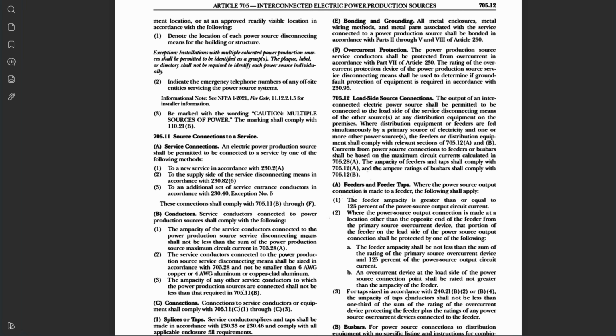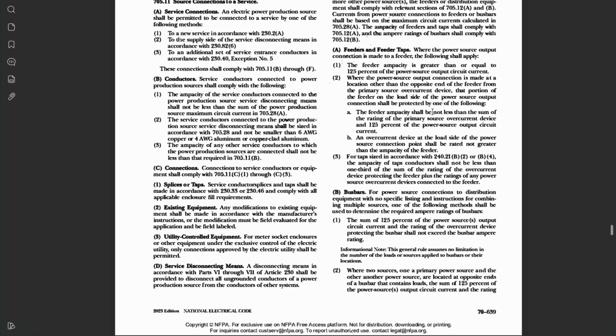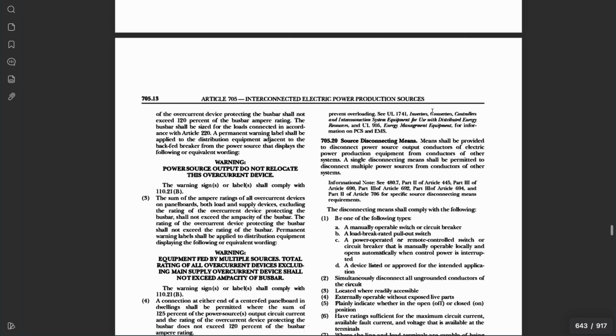To understand why, we need to talk about something called the 120% rule, which can be found in NEC article 705.12. This rule has been part of the National Electrical Code for many, many years and is used when connecting solar or battery systems to the load side of an electrical panel. The rule essentially limits how much power can be fed back into the panel through solar or battery breakers.